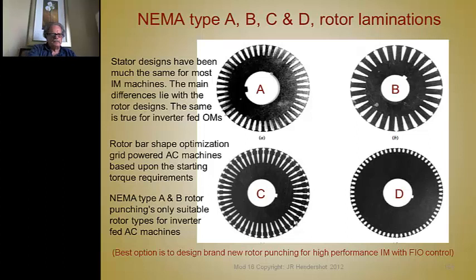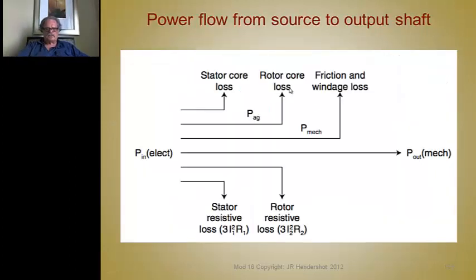The rotor bar shape has been optimized for the starting torque requirements, and only NEMA A and B is suitable for inverter operation. These other two aren't suitable for inverter operation, so you wouldn't want to use them. And even the type A and B for a certain frame size might need to be modified slightly to get the best performance out of a machine that size using the inverter. So let's look at what those differences are.